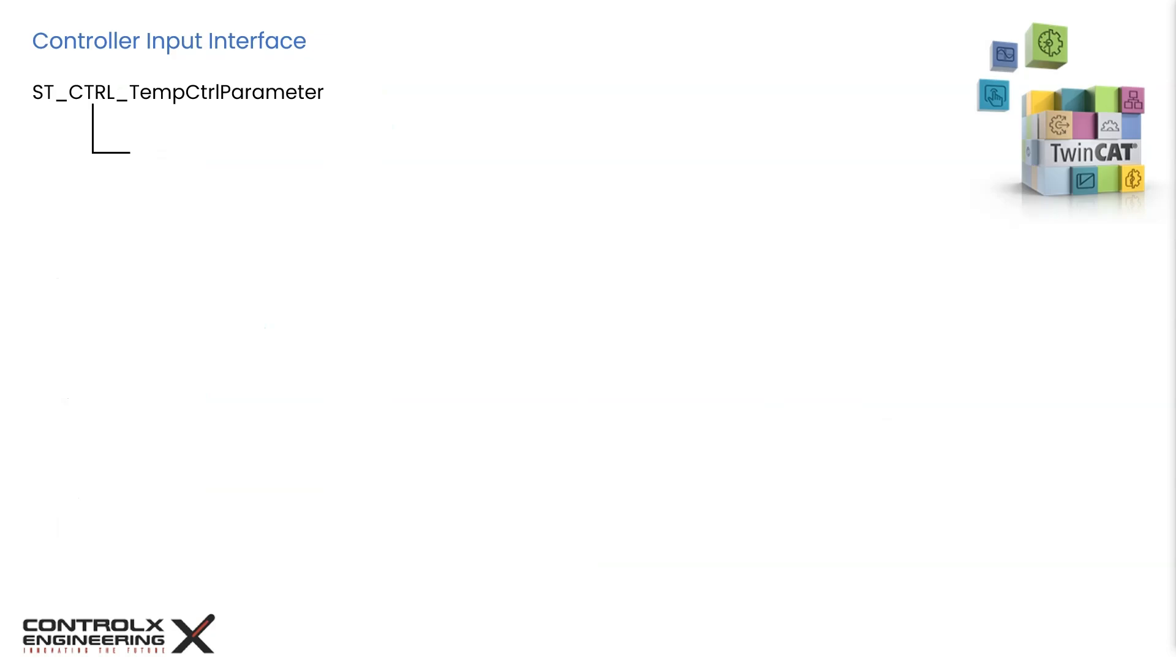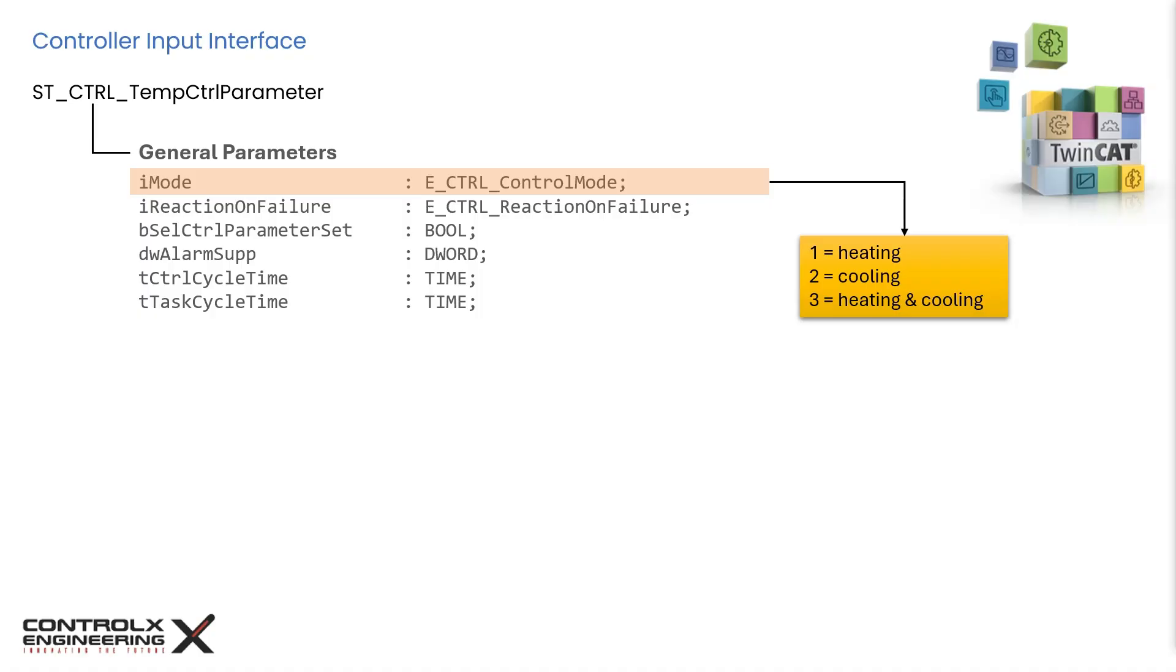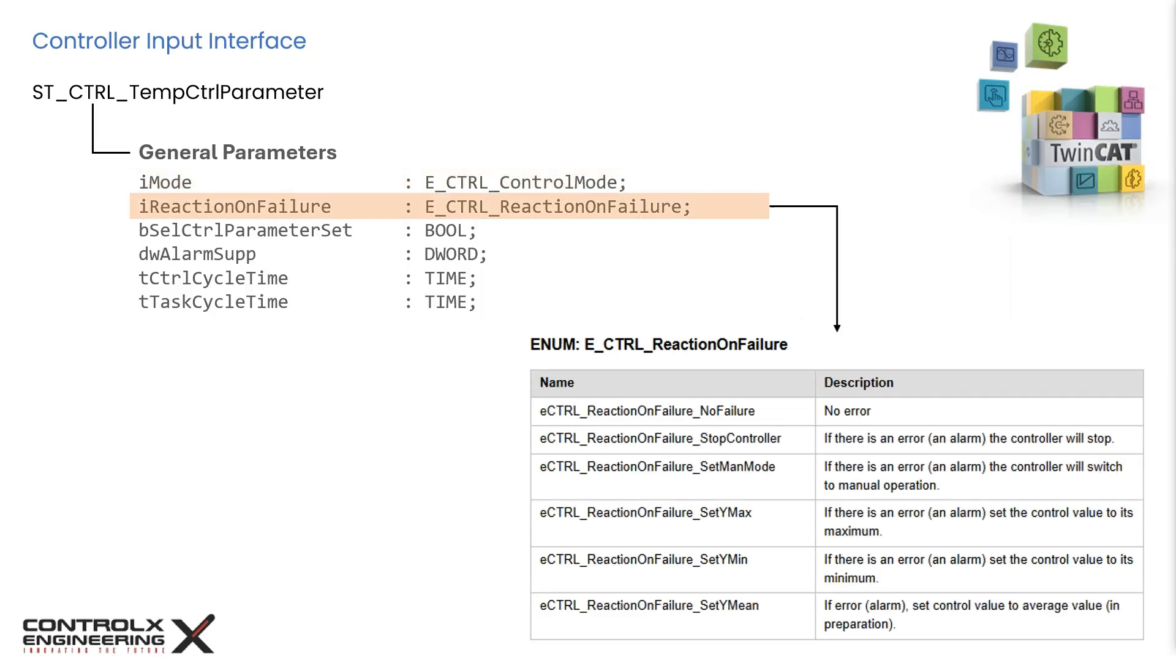Since this structure contains a lot of parameters, we will review them as groups. First let's look at the general parameter group. The input I mode determines the controller operation mode. We can make the selection based on our application. Some applications only require active heating while some require both heating and cooling. With this parameter we can specify the action to take during controller failure. The input action can be specified based on one of the available enumerations shown here. We can either select no action or stop the controller on error or switch from active mode to manual mode for example.